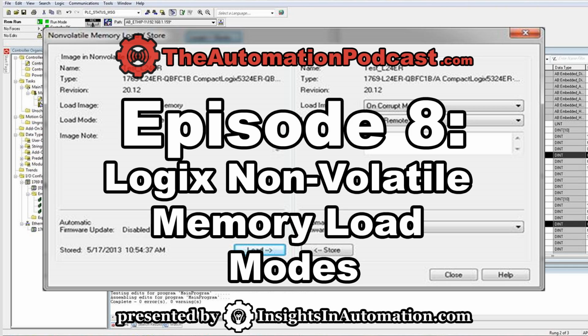Go into controller properties, go into the non-volatile memory tab, click on the load button, and after a few seconds or minutes, our program 1 should be reloaded from the non-volatile memory into the controller's memory. So reconnect to the processor and verify that program 2 has been wiped out by program 1. Okay, so test 1 went well.